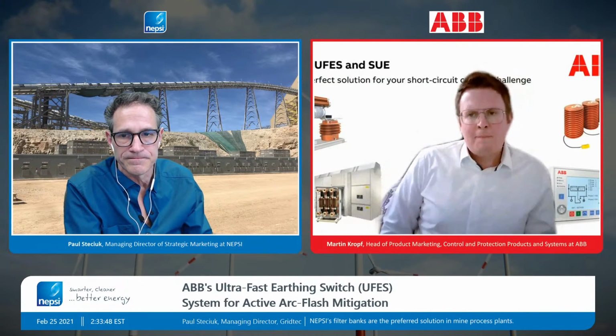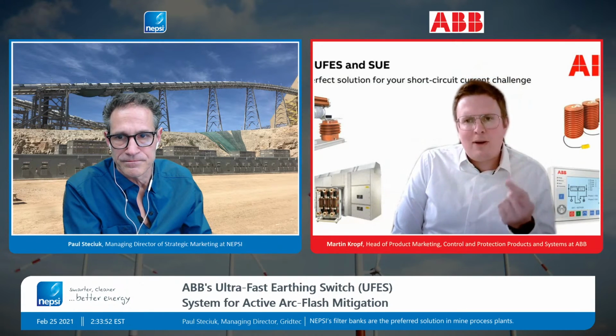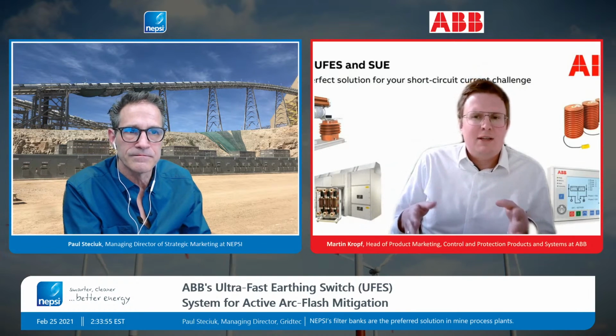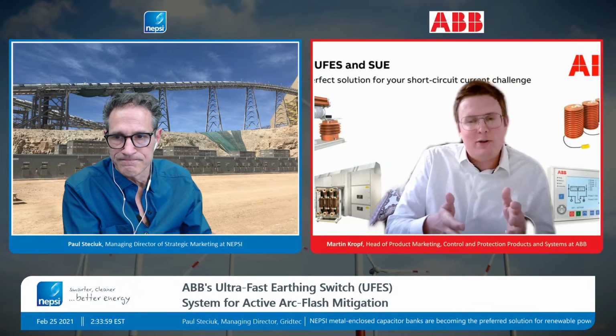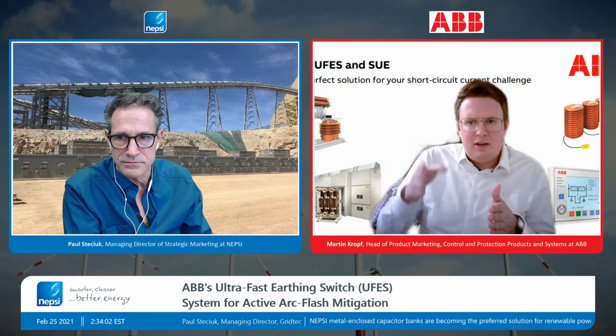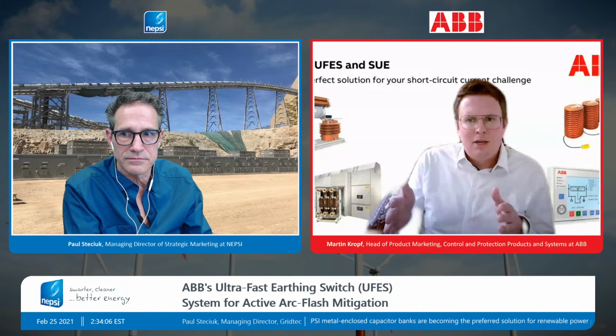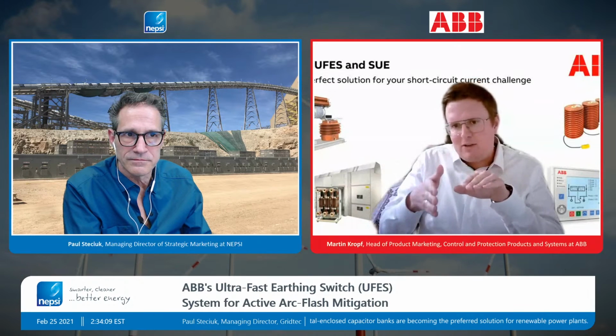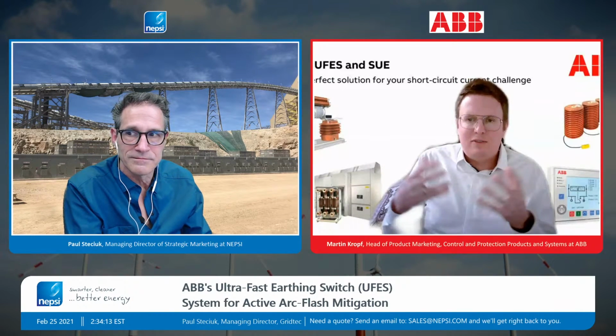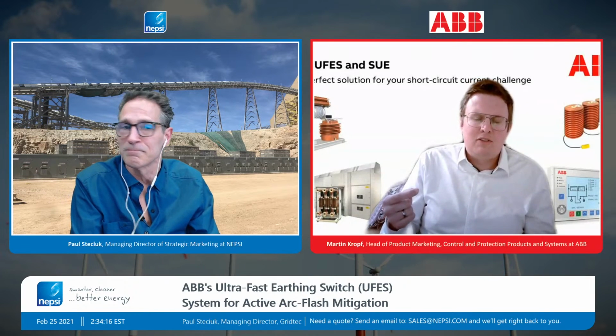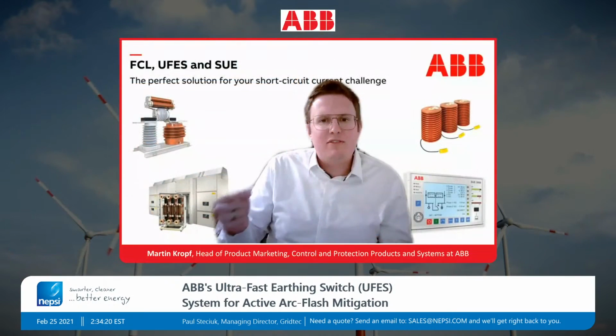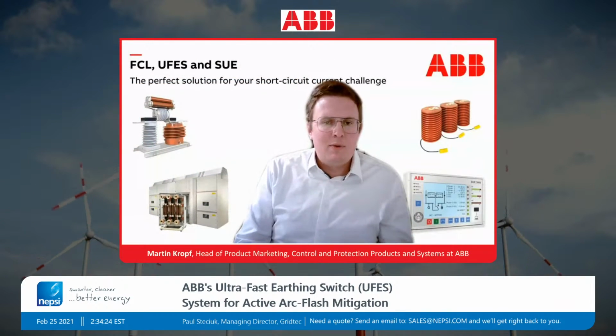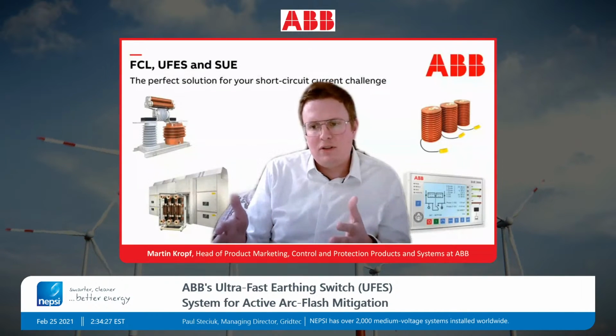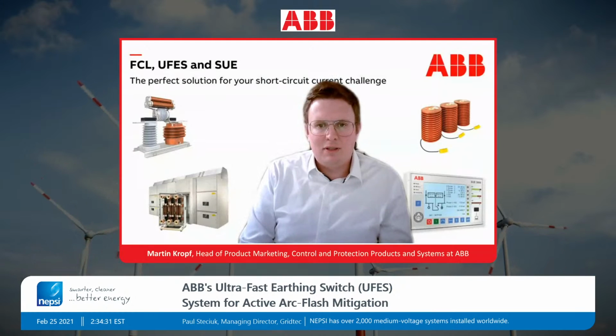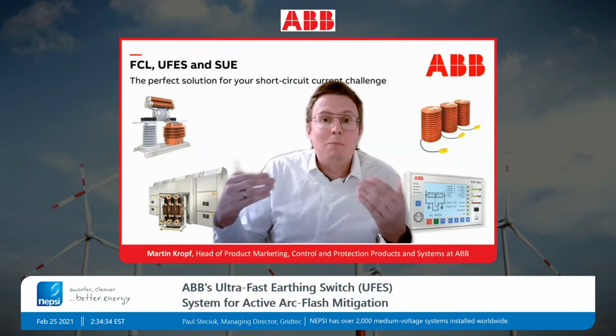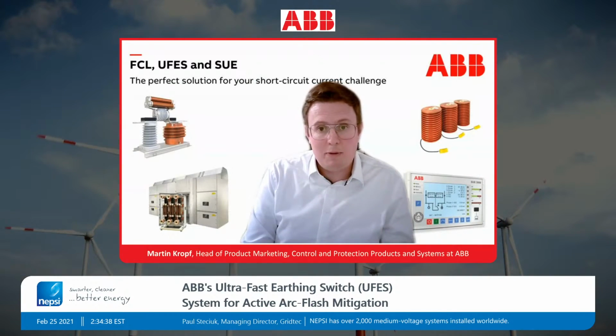Good point. What we are doing is a three-phase fault, because the background is that normally in a medium voltage application, a switchgear, or also in a capacitor bank application, the arc starts at one phase, but normally it's a non-segregated system. So you have the bus bars beside, and there is no segregation between. What we have seen is the arcing starting at one phase, but then normally commutating into a three-phase fault. So we have the three-phase fault anyway, which will then be interrupted by a three-phase bolted connection. We are not making phase-wise tripping with the ultra-fast earthing switch.